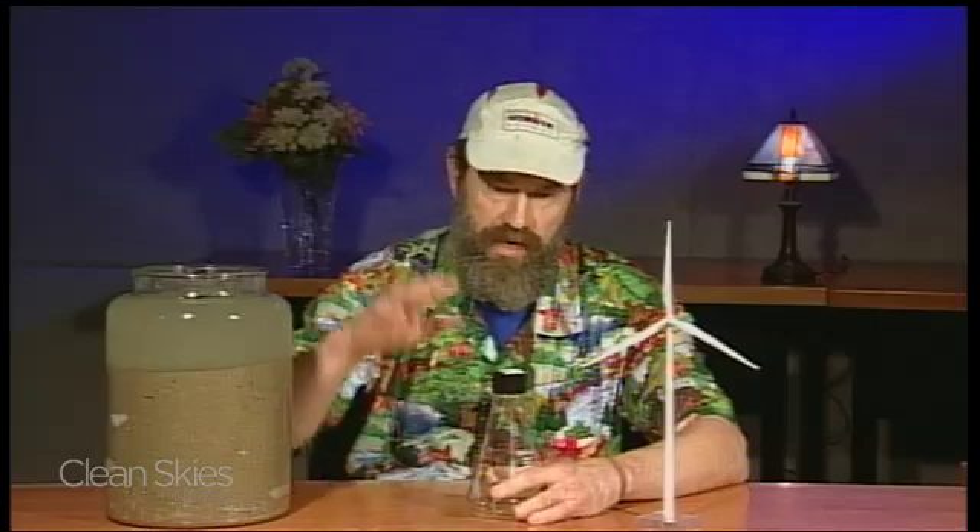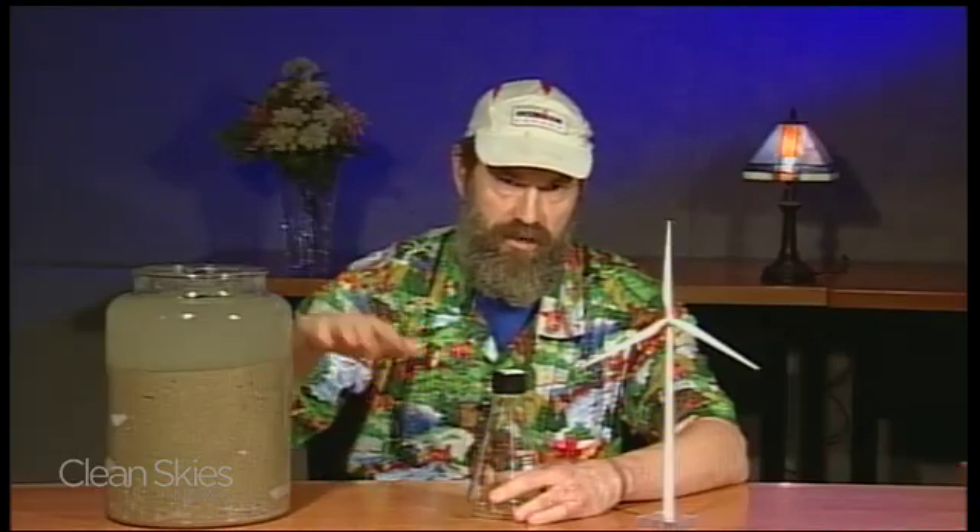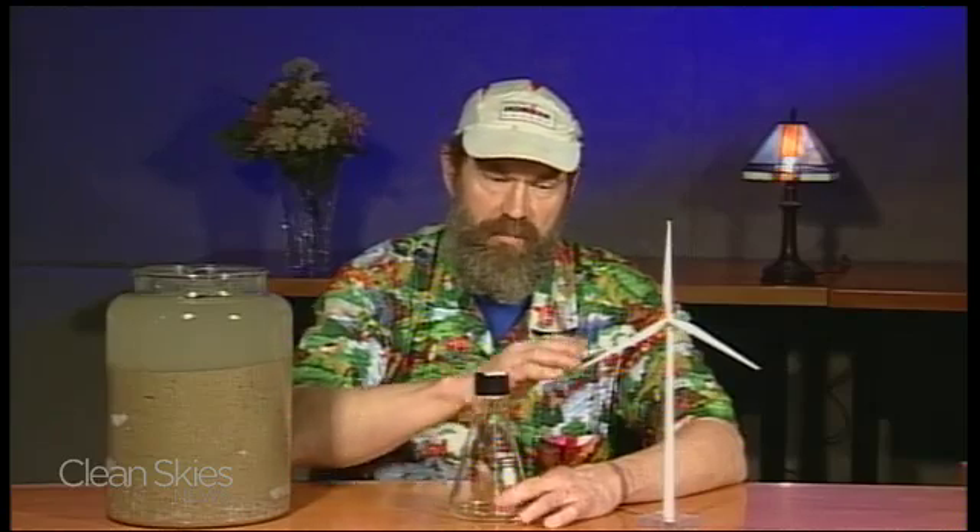The large structures you would need — a sphere about 32 to 33 meters in diameter, 300 meters below the surface of the ocean, which is off our continental shelf right here — would store about 10 megawatt hours of electricity. The cost, including tugging this thing out and sinking it down, would be about $200 to $300 per kilowatt hour when these things are finally made in volume. We could start ramping up fairly quickly, building a little system, then a bigger system, then the final system in a ramp-up of two, three, four years.